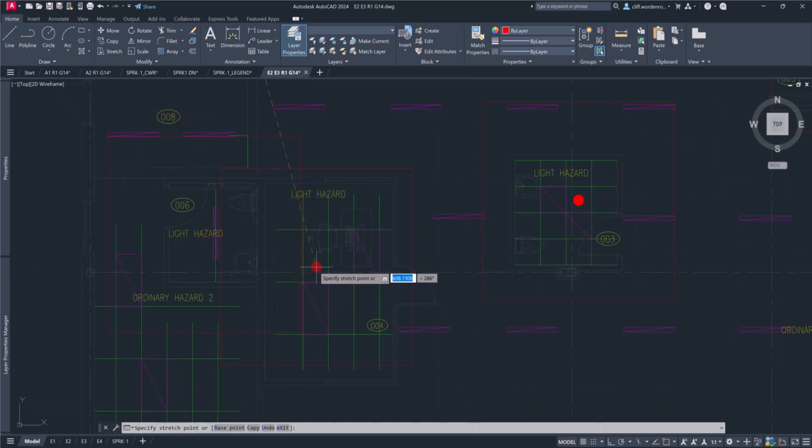Right now, I'm competing with the light. Ideally, I could put it somewhere like here, which would pretty much cover the wall. However, I can't do that because I've got this T-bar lay-in. So this one is going to require 2 sprinklers in this room. So I'm going to center it. And again, this is going to be approximate. I'm going to put one here.